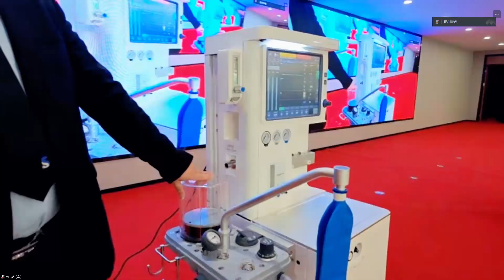And of course, with this one you already have the bypass function. So even if the operation time is more than 8 or 10 hours, for some very complex operations, we can very easily change the canister and the gas will never leak. You never need to change to manual ventilation—only the mechanical part is involved.